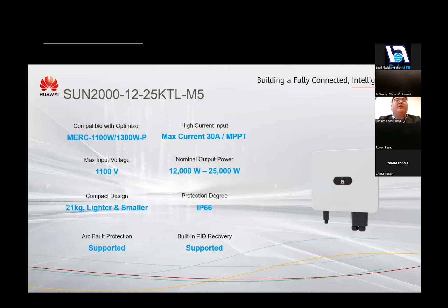12 to 25 kTL M5 is a new model to replace the 12 to 20 kTL M2. So you can see there's a new model, the 25 kTL, which was not available before. And the same as the 50 kTL, it is compatible with our new generation optimizer, and the current input of each MPPT is the same at 30 amps. And the weight is only 21 kg, so it's very easy to handle on site. And the protection rating is IP66. You can install it indoor or outdoor.